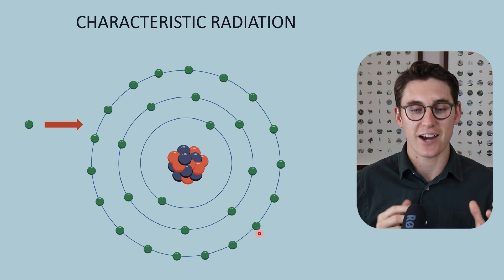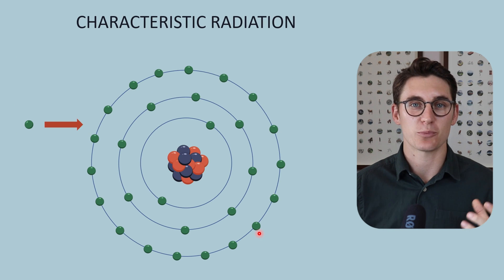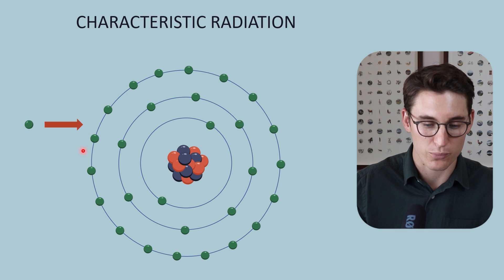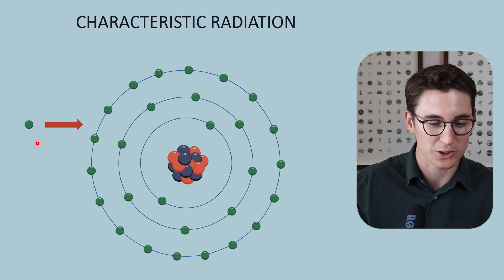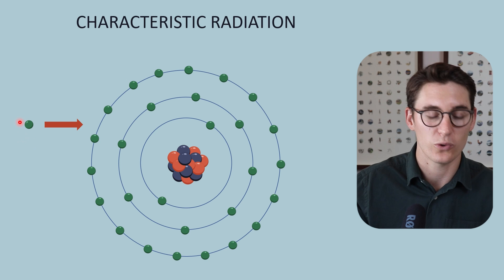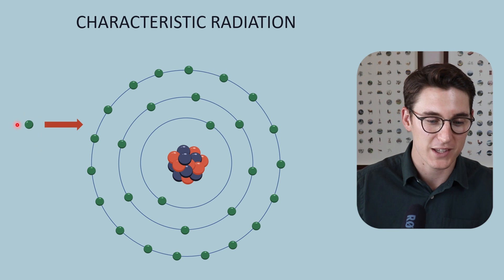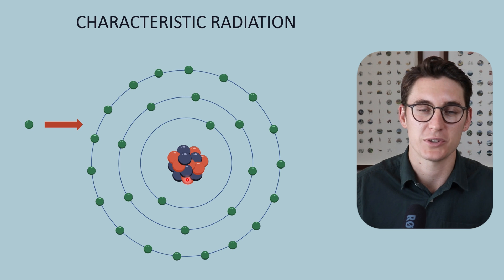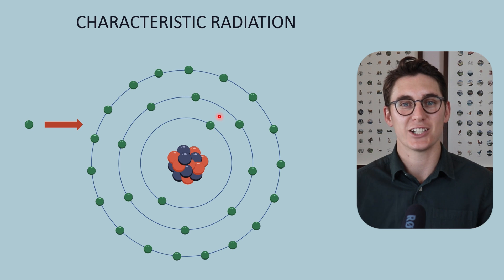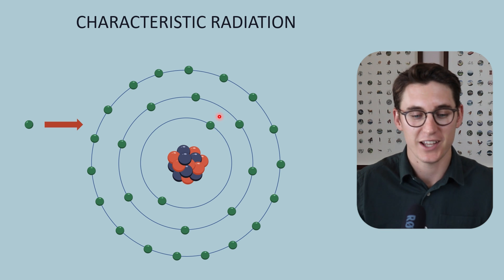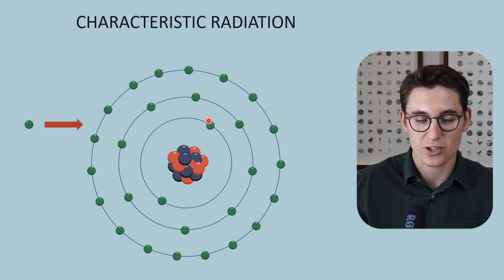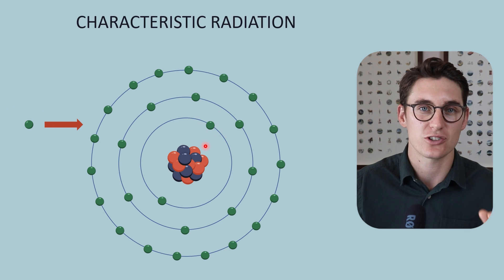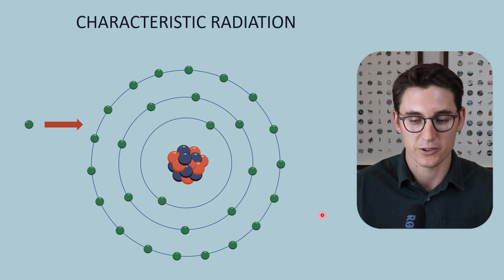So how exactly does characteristic radiation production occur? When we looked at Bremsstrahlung radiation, we saw that that was an interaction between the striking electron — the accelerated electron from the cathode — and the nucleus of our target material. Characteristic radiation differs in the fact that this bombarding electron interacts with inner shell electrons of our anode target material.